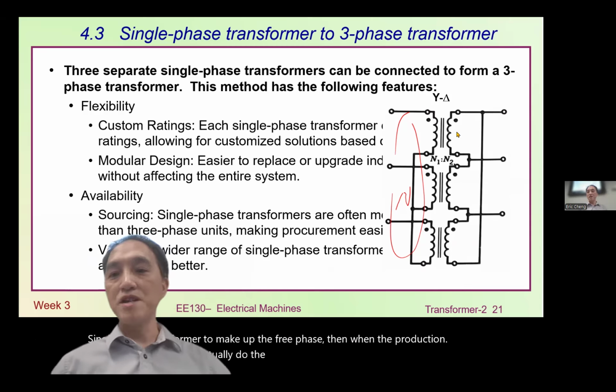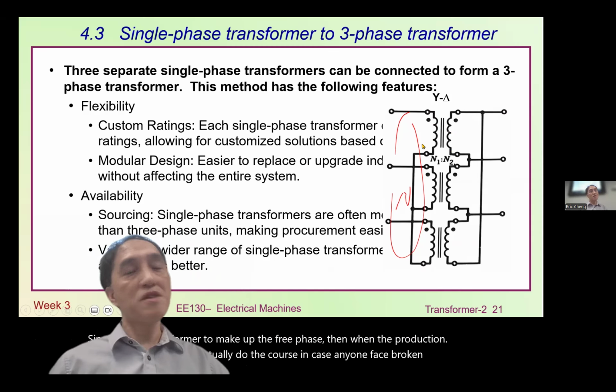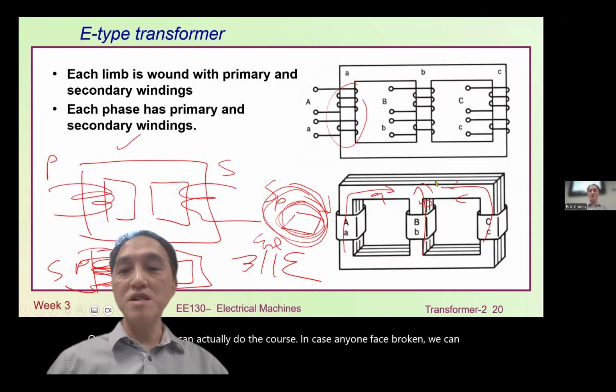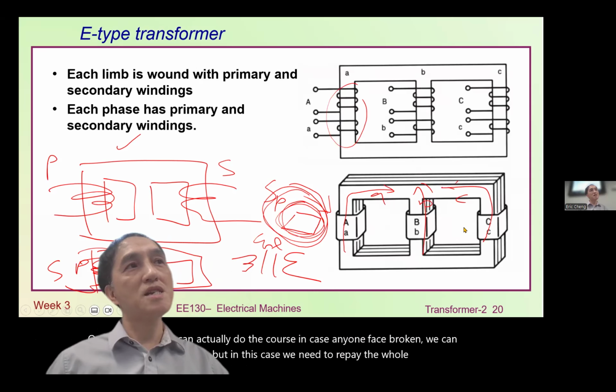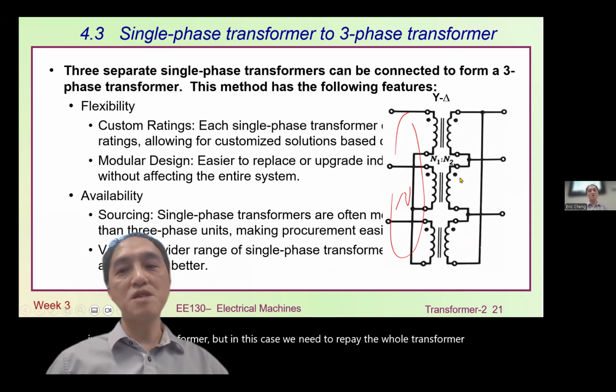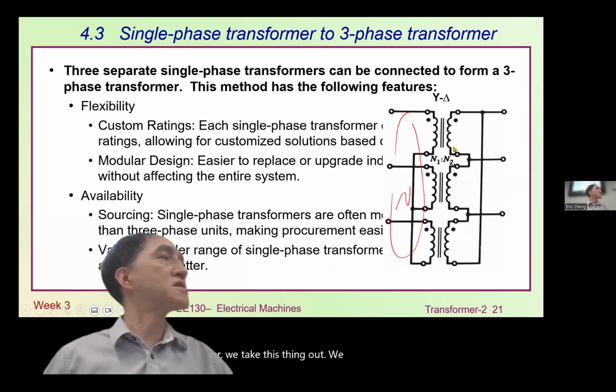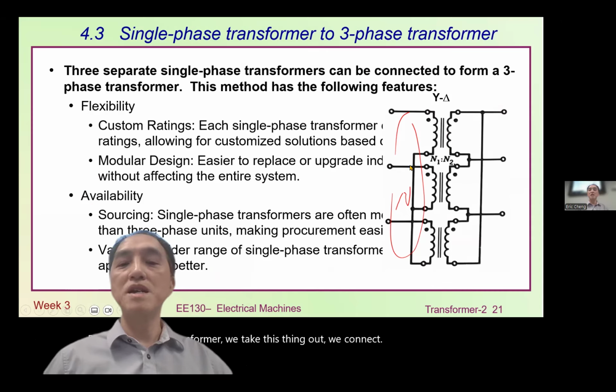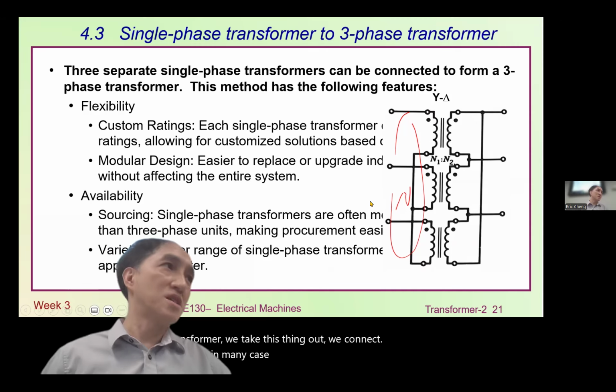In case any one phase is broken, we can just replace one transformer. But with a combined transformer, we need to replace the whole thing, which is expensive. With separate transformers, we take the one out, reconnect, and save cost. So in many cases, this does have some advantage.